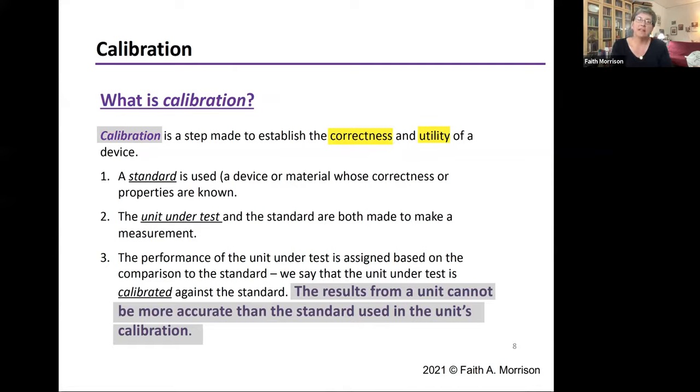So the last line on my slide says that the results from a unit can't be more accurate than the standard used in calibrating the device. So there's no way that I can take this device of measuring yardage of fabric and get the length of that fabric to a ten thousandth of an inch. The device I calibrated it with is not good to that level.